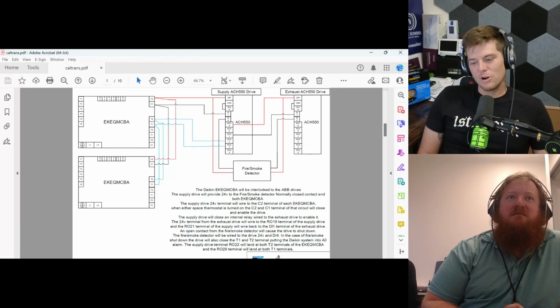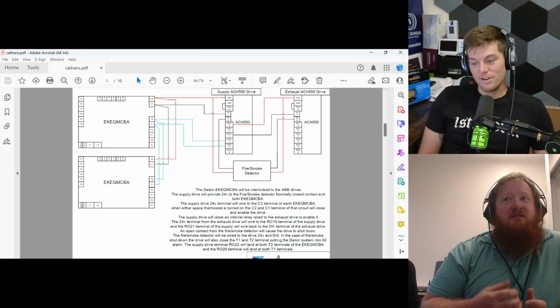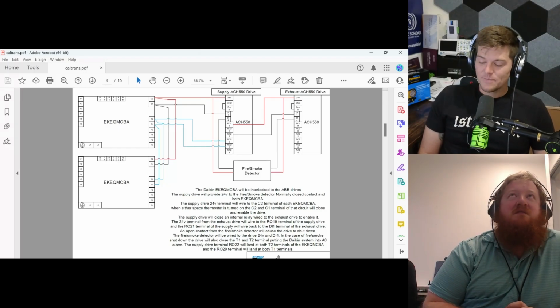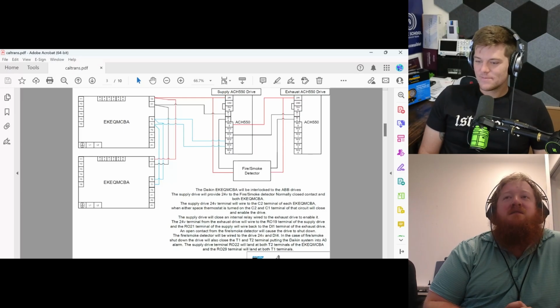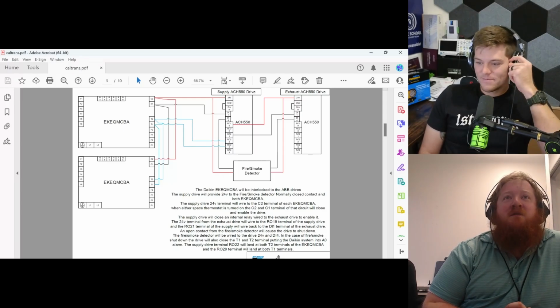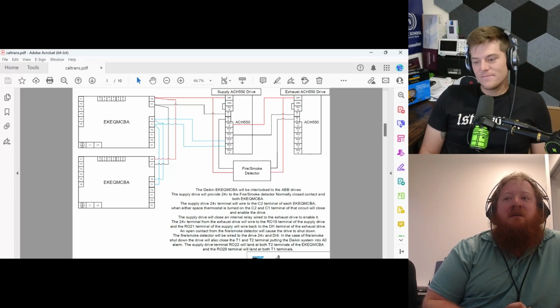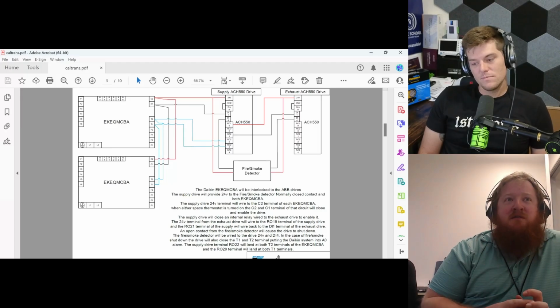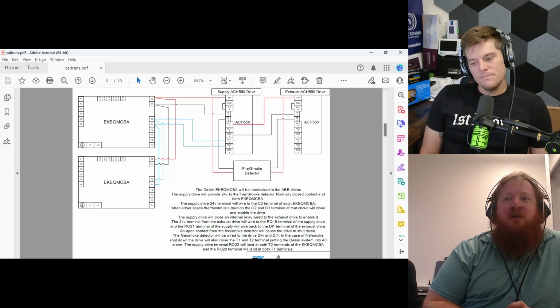But it shouldn't require you to manually touch a button to clear it. I think it should be automatic, absolutely, because there are so many situations - say you actually do have a fire and that smoke detector trips, but the building automation system isn't integrated and it's just a standalone project like this. If that signal clears but there's still stuff going on in the building that could potentially be harmful to human occupants, we don't want it to automatically reset.